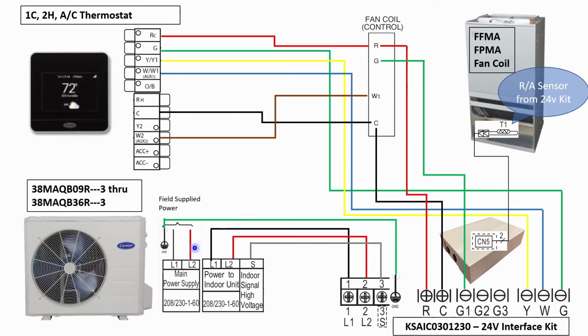Our high voltage wiring from the ductless outdoor unit to the 24-volt interface kit, we use L1, L2, S, and ground, and it'll go to the connection that says indoor unit on the 24-volt interface kit. The diagram also shows where you have to connect to CN5 on the 24-volt interface kit, the thermistor that's going to sense the return air temperature. Without this being installed, the system will not operate.